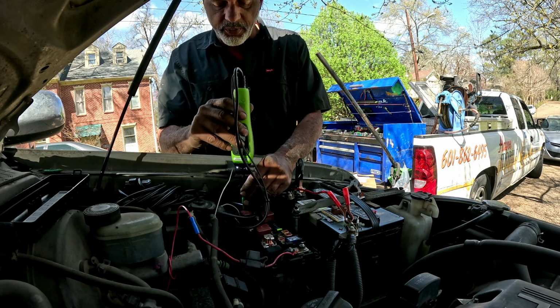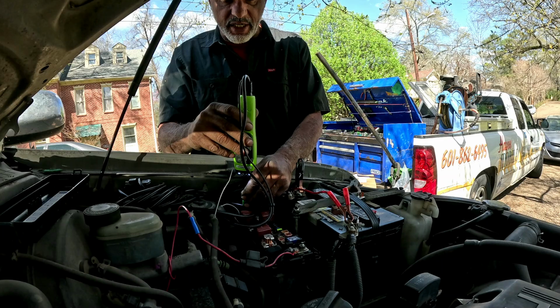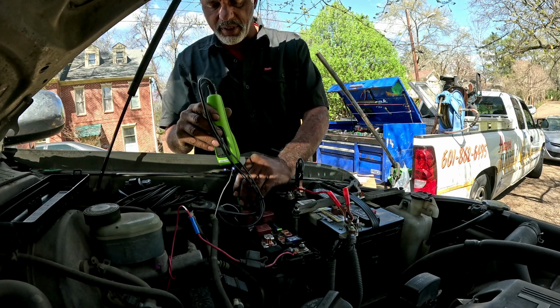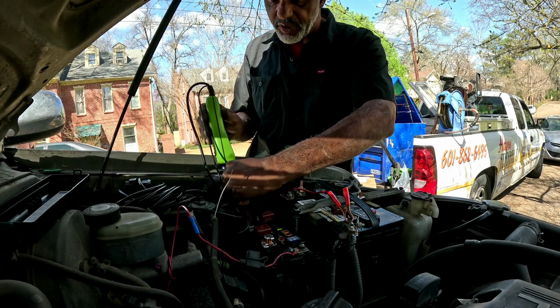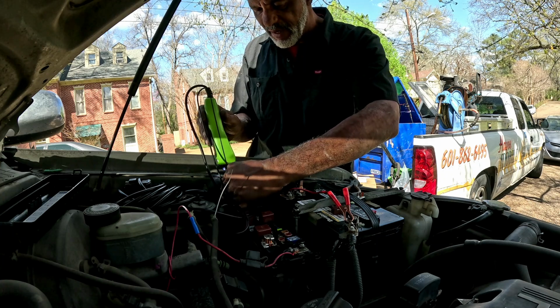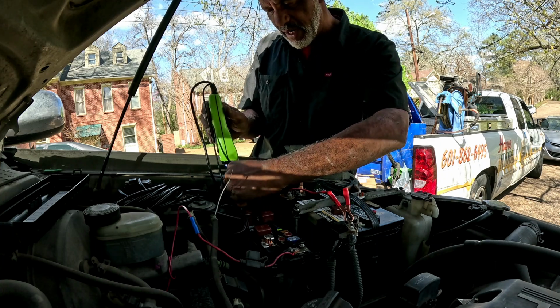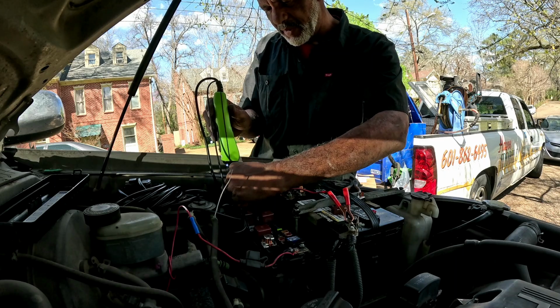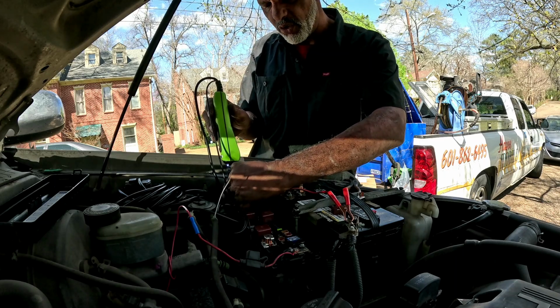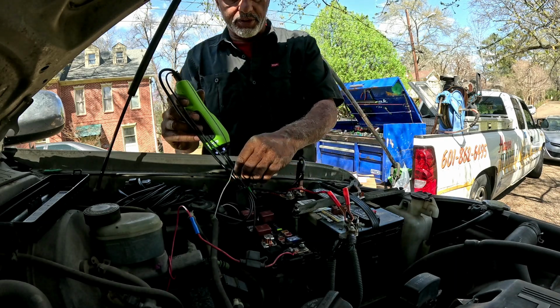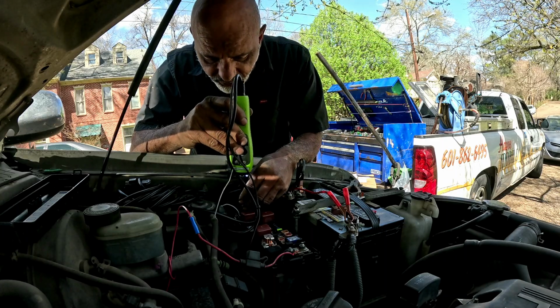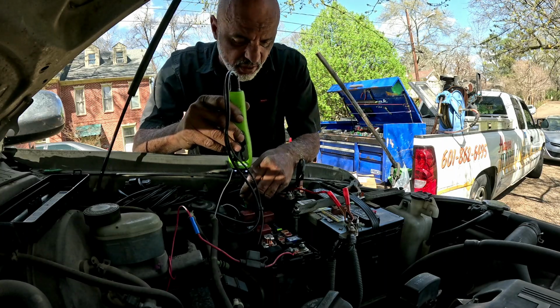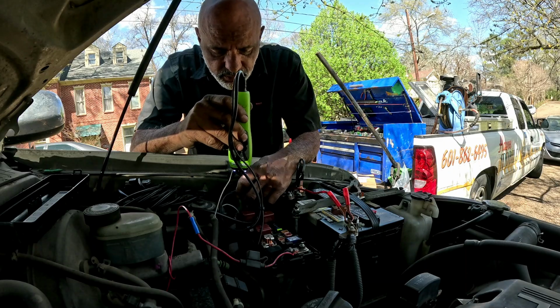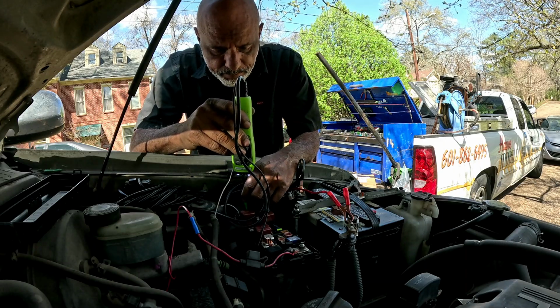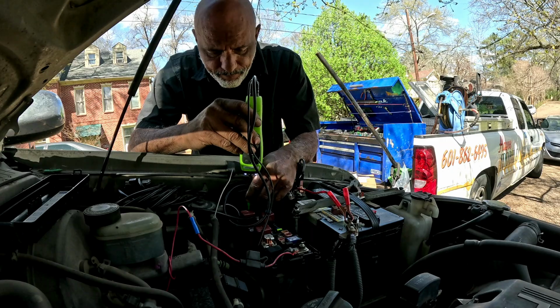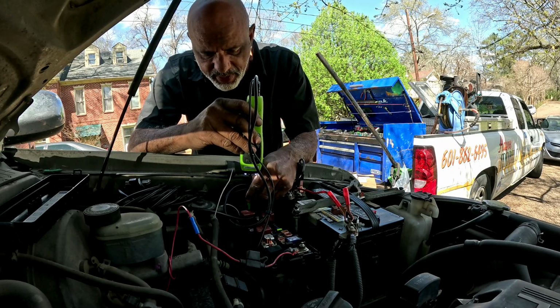Let's go to the opening relay. I got 12 volts on the opening relay on the control side. I have nothing, no ground or anything coming from the other side of the opening. So there's no ground or anything on that. I got voltage coming out of my load. Okay, and I have voltage coming out of my load.